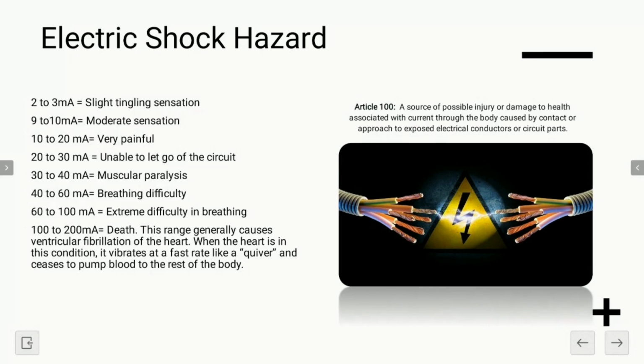If you think about this, when are your GFCIs designed to trip, if they're working correctly with no common neutral problems? How many milliamps are they supposed to trip at? Any guesses? Between 4 to 6 milliamps. So if your GFCIs are working correctly and there are no common neutral issues, they should trip before you even get to this moderate sensation.